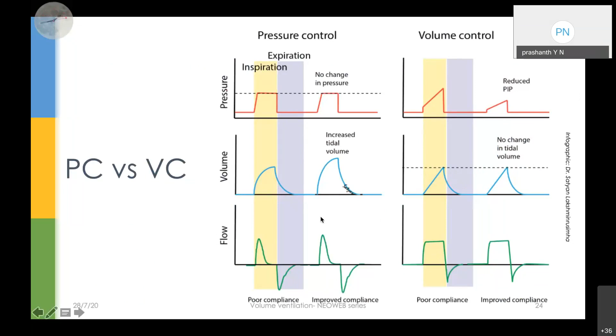Okay, so let's come to volume control ventilation. When I'm talking about volume control ventilation, I want you to realize that I'm not talking about guarantee yet. I'm just controlling the volumes. The operator selects the tidal volume and the respiratory rate, as we just discussed in the previous slide. I'm just telling the ventilator to give this much tidal volume into the circuit. That's what the operator is saying. And the ventilator, what will it do? It just mechanically delivers a constant preset VT.